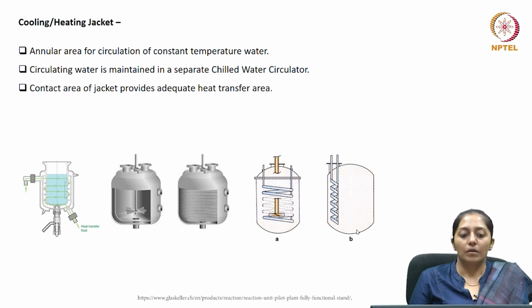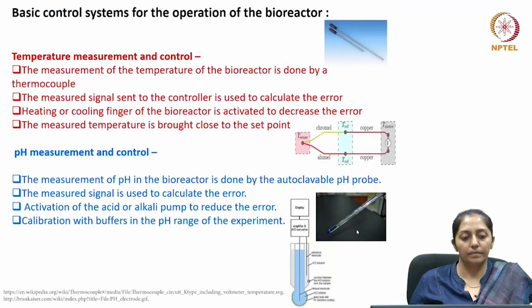There can be water coming from the chilling unit which is circulated around the entire reactor body, or if the reactor volume is very small, then you can have heating or cooling fingers inserted inside the reactor, through which the chilled water from the chilling unit is circulated for maintenance of the temperature of the liquid broth inside the reactor.